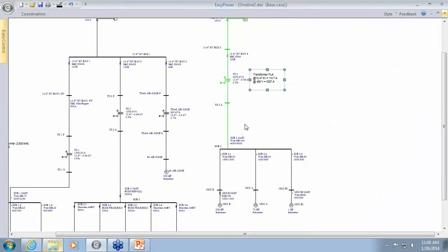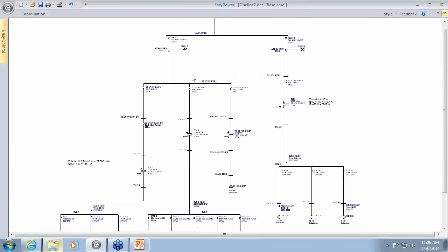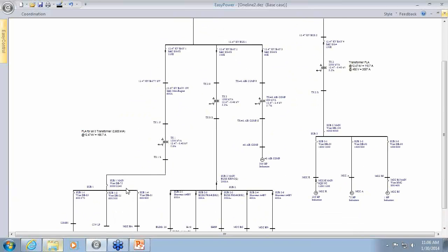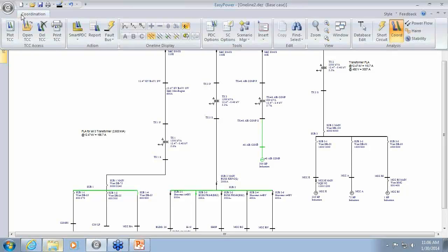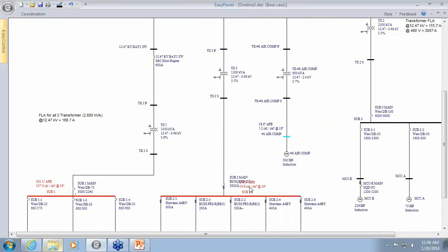I know I've gone a little long here. I just have a couple more things to mention regarding this relay here. Under normal operation, the incident energy at each of these equipment. Let's fault these. One was 107, this one's 54, this one's 1.2.